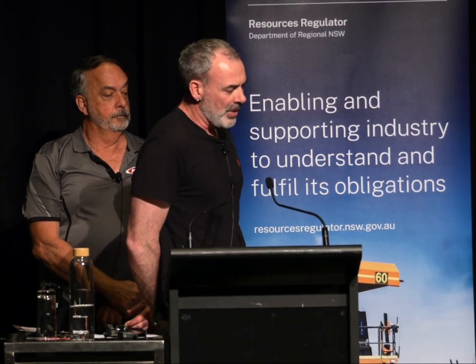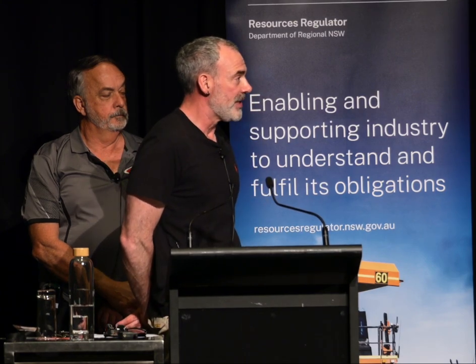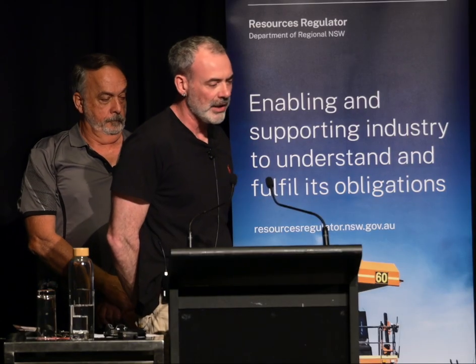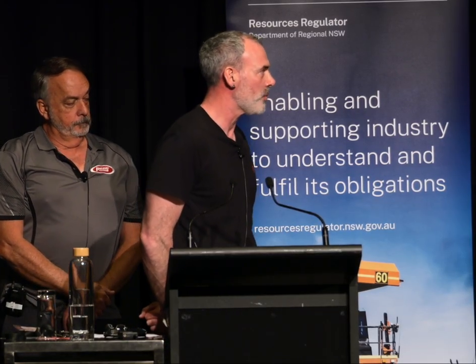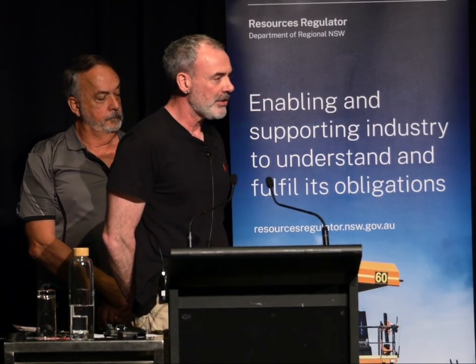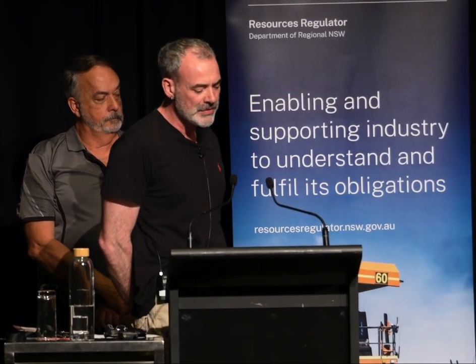So I'll just finish off by saying, transformers are reliable machines. Transformer reliability surveys from the likes of CIGRE specify that failure rates across all voltage classes are less than 1%. But in New South Wales, only a couple of months ago, a 200 MVA transformer caught fire down near to Tallawarra Power Station.